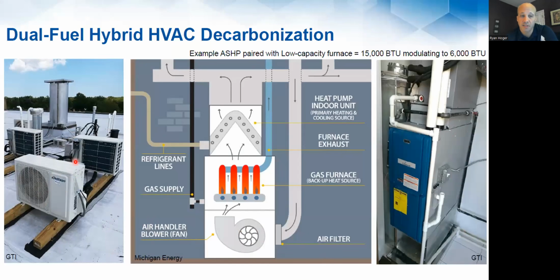So what's actually happening is my outdoor equipment, a heat pump in this case, has refrigerant lines going to the coil above my furnace, just like my air conditioner did. I have supply duct leaving. I have return duct coming in. I have a gas line coming in like my furnace had. I have a flue going out like my furnace had. It's identical to everything that I had in my furnace.